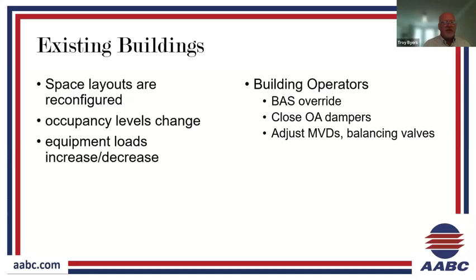Occupancy levels we've touched on can change. Equipment loads increasing and decreasing, and that could be lighting, it could be, again, occupants, computers, any heat producing refrigerators, things like that. Anything that's going to provide a heat load. All of that needs to be taken into account, and these things do change over time in existing buildings. I didn't ask the question if we have any building operators in here, but I don't think we have any. I can go ahead and pick on them because they're not here.